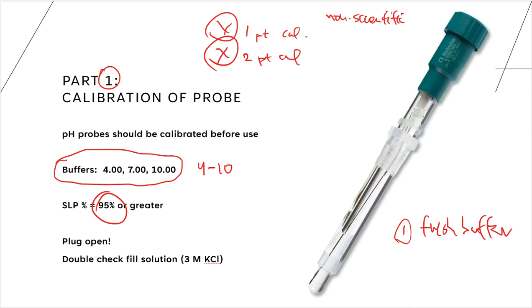And then if fresh buffer doesn't work, then I'm going to monitor this on each buffer, because I know what each buffer should read in terms of millivolts. So if I put the probe into the buffer one by one and just measure it, I'll be able to see the response from the probe in that buffer to see if any one of the three is a problem. Because if I can find that one that keeps triggering an error, then I can replace that one and maybe get a much better number here on the end. So there's a couple of ways that we can fix slope percents that are very low, and those are two of the easiest ways that we can do that.